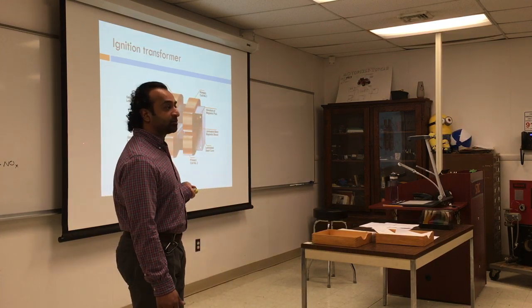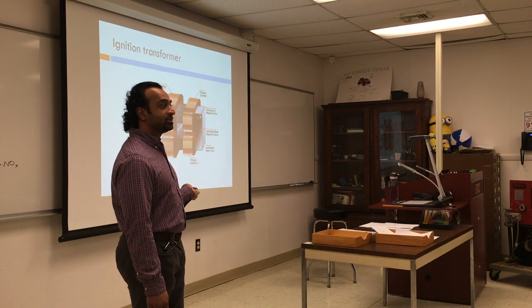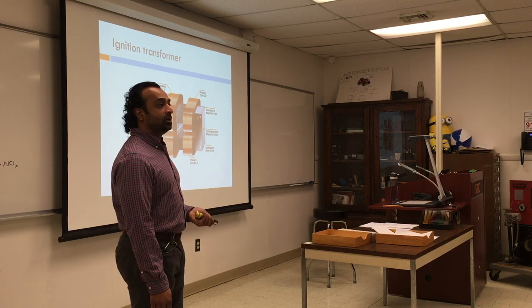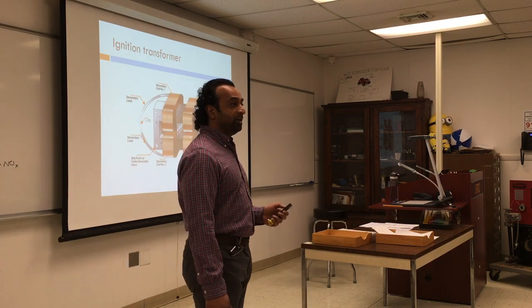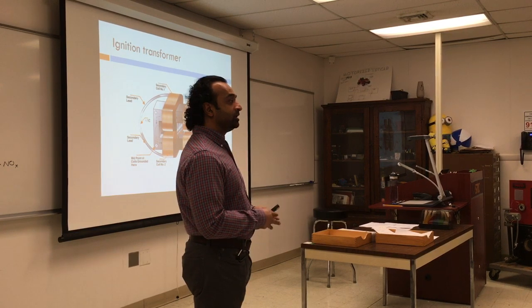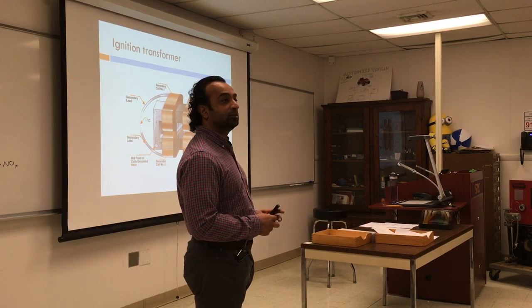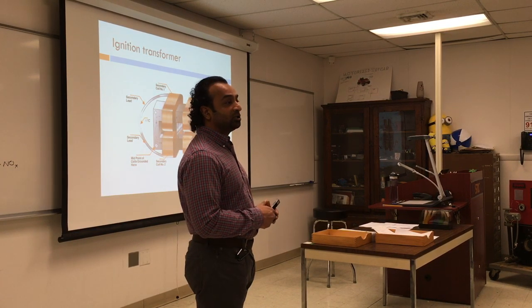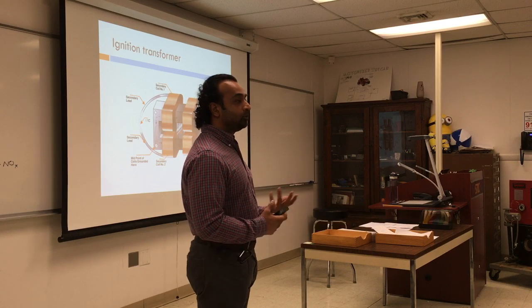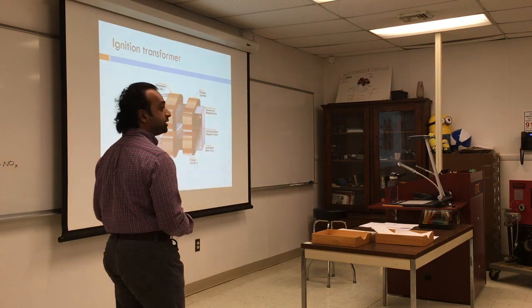So if we have a weak spark, it's not going to ignite as fast. It will take at least the 3 trials, then it will go in safety. So we have to try for ignition 3 times. If we do not do that, it will go in safety. So to keep it from going in safety, you have to check those little things. And it could be a little bit challenging to know why it is going in safety.